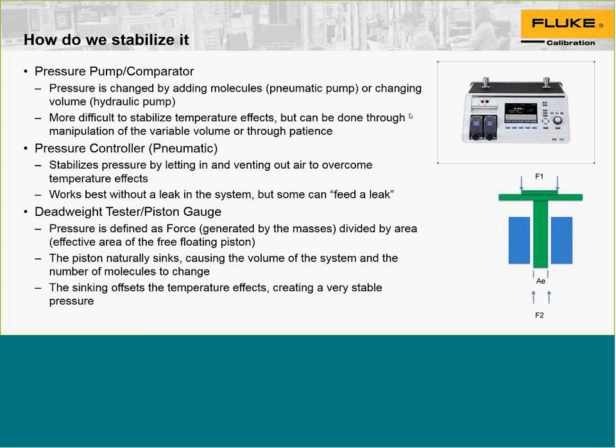That is the difference between a leak, the number of molecules leaving the system, and temperature effects: the temperature effects eventually dissipate and go away. That is, you generate the pressure, you turn the screw press, and the pressure will decrease due to the temperature effects, but the decrease will slow down, and eventually your pressure will stabilize. It may take a few minutes, though, to get there. A leak stabilizes pressure in a very much different way.